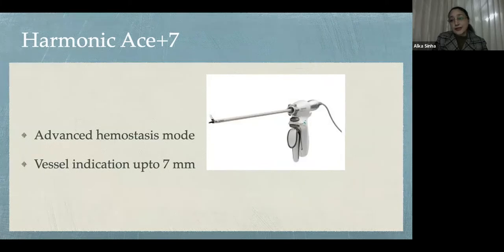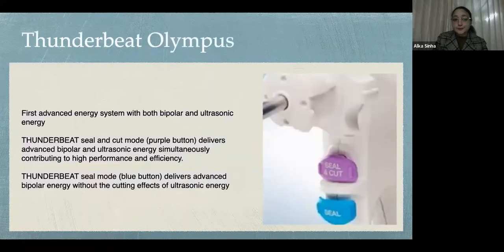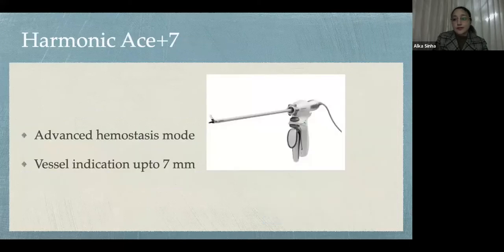Because the vessel sealing was only up to 5 millimeters, that was a drawback. Ethicon Harmonic solved it by bringing out the Harmonic Ace Plus 7, which had an advanced hemostasis mode with vessel sealing of up to 7 millimeters. Because it was 7 millimeters, that made it comparable to the other advanced bipolar devices and the vessel sealing achieved by those devices, while having the benefit of ultrasonic dissection also.